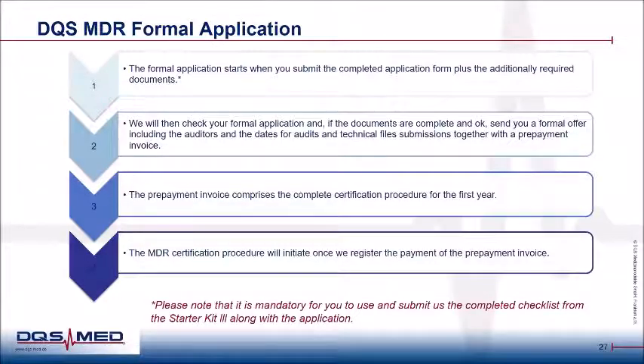The next step is the formal application. That means you file the technical documentation to us, you file the application form sheet to us, and any additionally required documents that are outlined in the procedure related to the device, depending on whether it's a class 3 device or whatsoever. There might be additional information requested, and for this step, we need all those documents at once. From the moment you file the application, we can start the technical file assessment whenever we are ready with the right auditor resource for that.